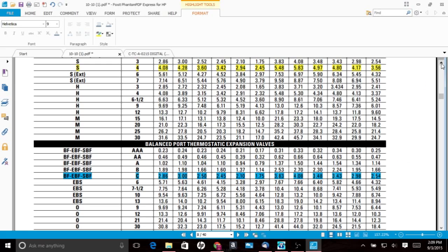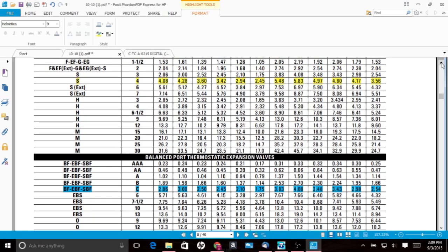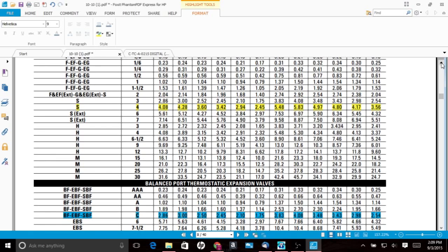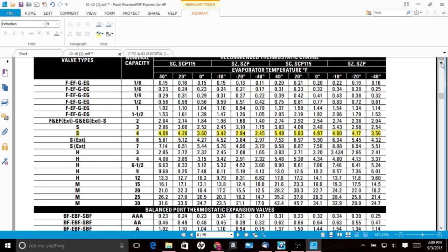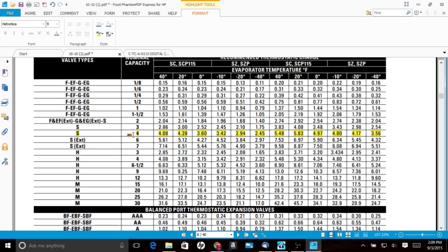One thing I do want to mention right now is that the manufacturers will supply you with the expansion valve that they have listed for their coil. And that is a great way to go about finding which TXV to use. In this case, I did end up calling Century, talked to their parts department over there and found out that this S-body valve is what they had listed for the coil and its nominal capacity is of 4 tons. So you can see here that somebody might look at that and say, well, I have an S-body valve and it's for a 4 ton nominal capacity. But you don't get 4 tons of capacity out of this valve until you get up to a plus 20 suction or plus 20 evap temp, same thing.